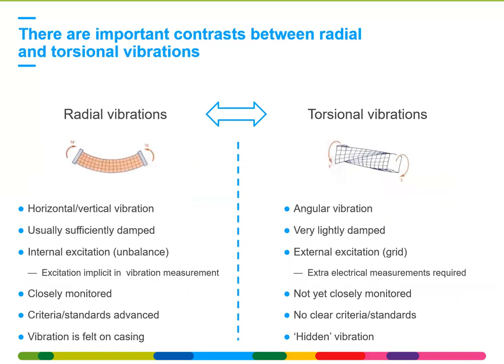For torsional vibrations, you're looking at angular vibrations, so it's in the rotational frame. They are very lightly damped, because you do not want your shaft line to have high damping in the rotational sense. This is why torsional vibrations by default have very light damping. The only damping comes from the material itself: the fact that you shear the material by deforming it gives a little bit of damping, but it's very low. The excitation typically comes from the grid, so it's outside of the power plant. And that's the main issue.